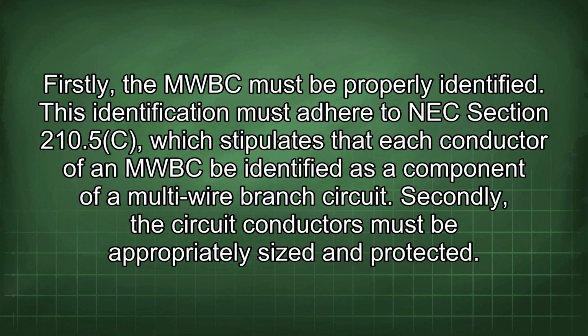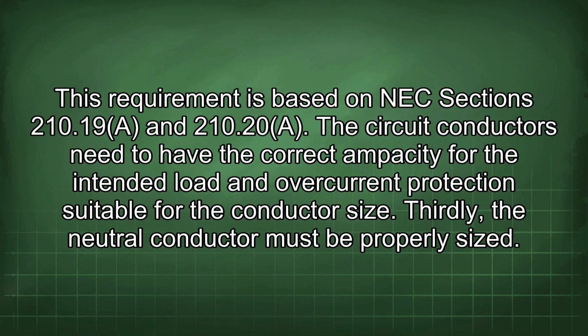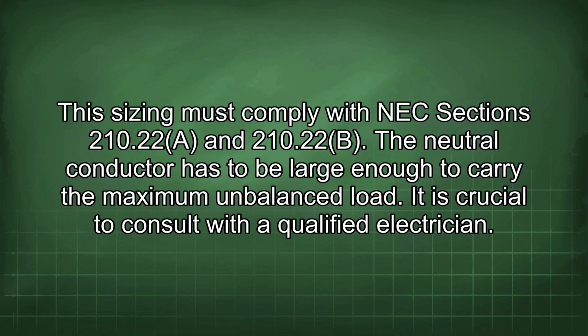Secondly, the circuit conductors must be appropriately sized and protected. This requirement is based on NEC Sections 210.19 and 210.20(A). The circuit conductors need to have the correct ampacity for the intended load and overcurrent protection suitable for the conductor size. Thirdly, the neutral conductor must be properly sized. This sizing must comply with NEC Sections 210.22 and 210.22(B). The neutral conductor has to be large enough to carry the maximum unbalanced load.